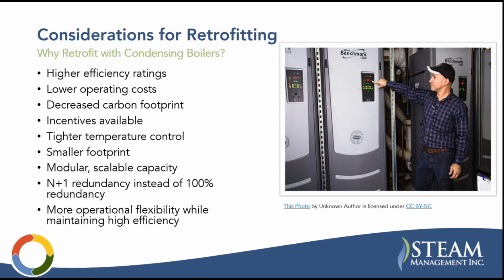And you can go with N+1 redundancy instead of 100% redundancy. So instead of sizing one large boiler to cover your load and then having 100% backup, you can replace that boiler with, say, 2 or 3 smaller condensing boilers, and then just have one extra, 50% or 33% loaded boiler for redundancy. It also provides more operational flexibility while maintaining high efficiency.